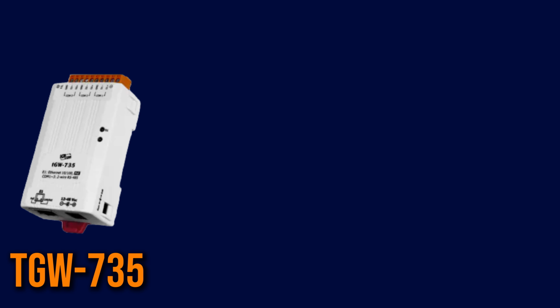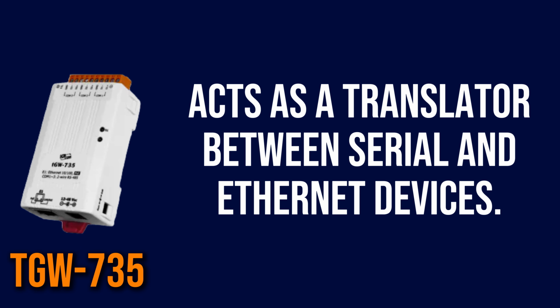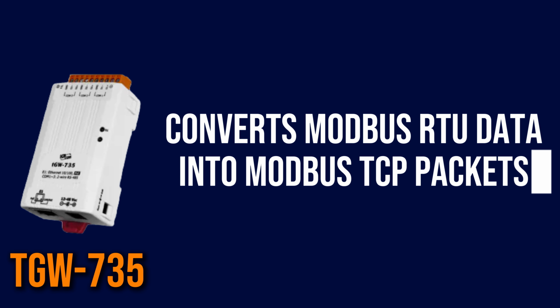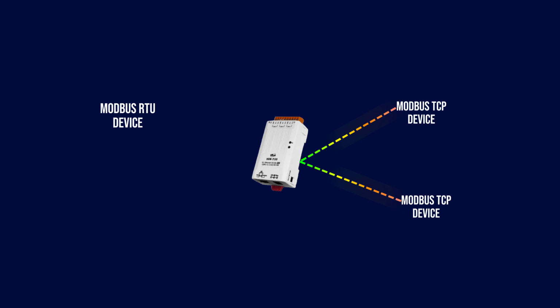The tGW series acts as a translator between serial and Ethernet devices. It converts Modbus RTU data from legacy equipment into Modbus TCP packets that can be read by modern Ethernet-based systems. This allows you to integrate older field devices into your existing infrastructure without having to rewire, reprogram, or replace any hardware. It's plug and play for your Modbus networks.